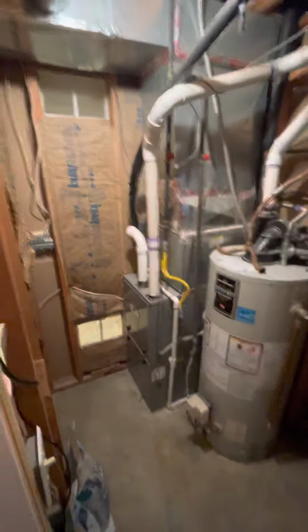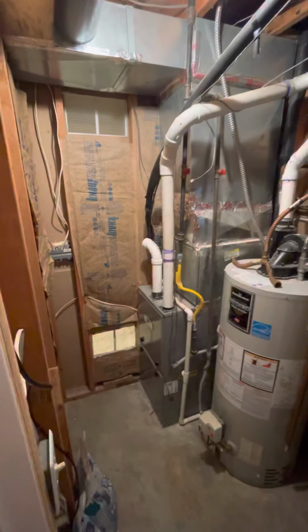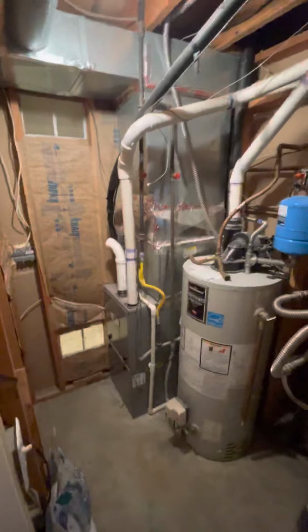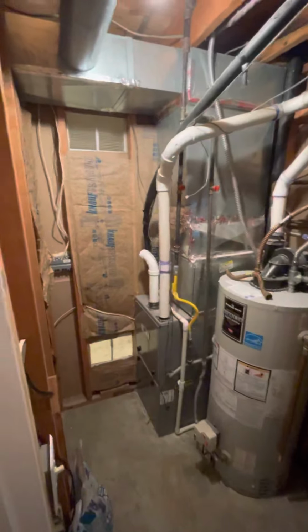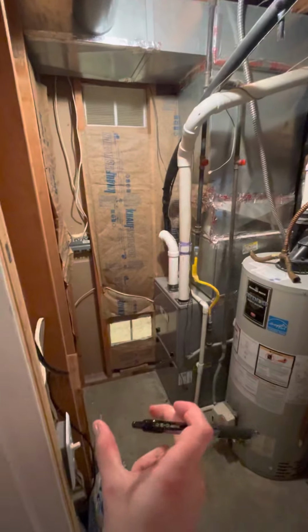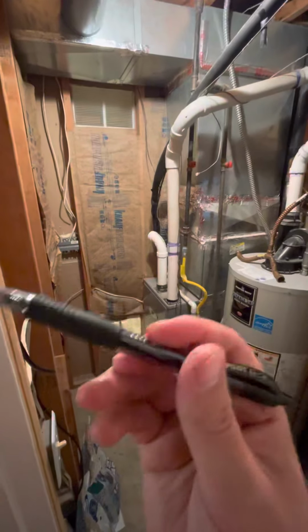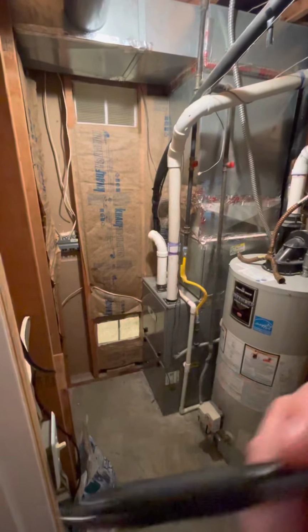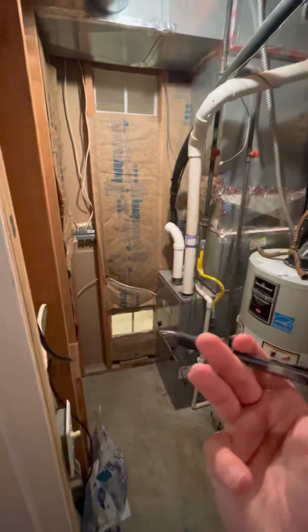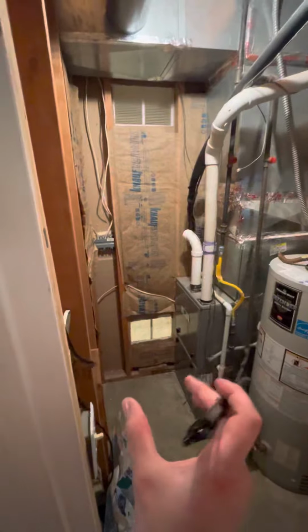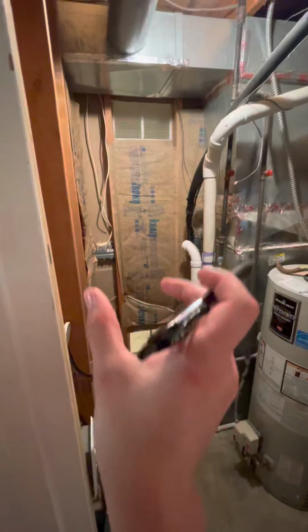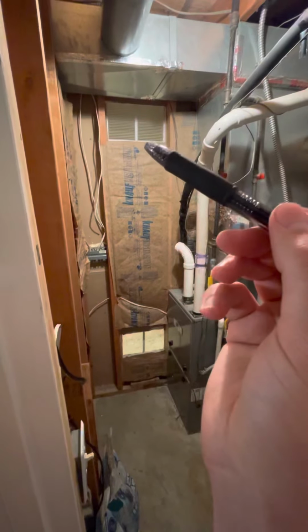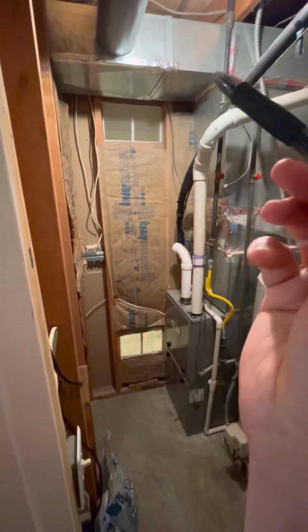So the main issue that they're having right now is that their main floor is obscenely hot and they're not getting really good airflow up there. So with moving the furnace, putting everything right here, stacking the AC on top of it, because the AC freezes, not functioning as well, and then the basement's frigid while the upstairs is really, really hot in the summer and the AC is not even keeping up. So the idea here would be to go ahead and put the system right here, hook it up to this existing ductwork right here, run either turning vanes going this direction or a high efficiency takeoff right there.